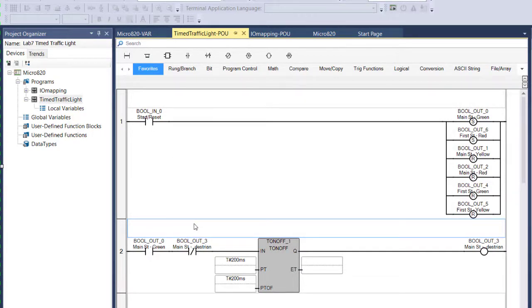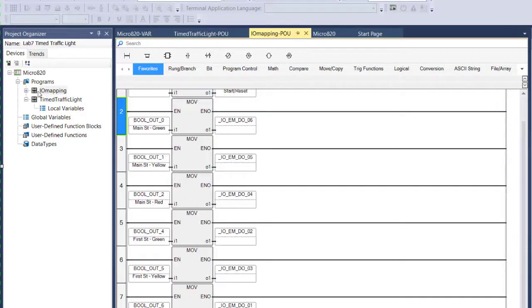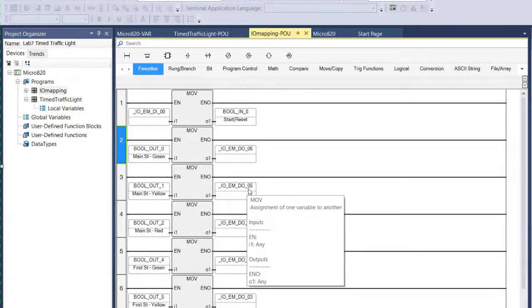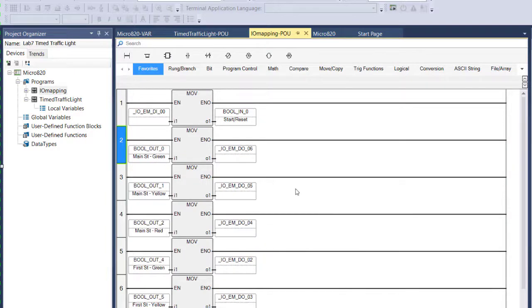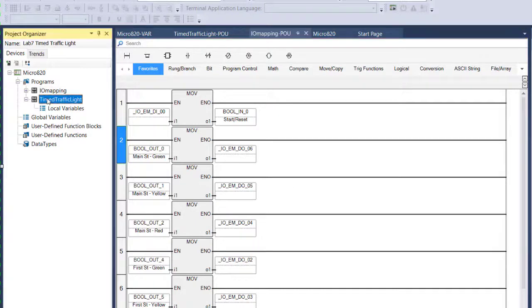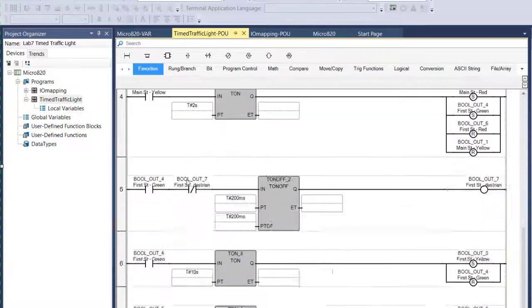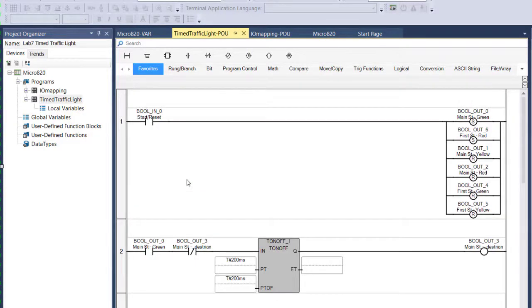If you remember, this program referenced global variables. It didn't reference input and outputs on a PLC directly. That's why we don't have to change this. That's the beauty of this principle I'm going to teach you about segregating I/O. You write a program and you don't reference I/O directly. You reference global variables. Then you simply create a new program. I've called mine IOMapping, where you map the input and output terminals to those global variables. The reason we do this is because what if the electrician who wires the control panel wires it slightly different than we anticipated. Maybe they wired one of the lights to a different output terminal than we thought. If I've segregated I/O, I just come to this program and I change the mapping.